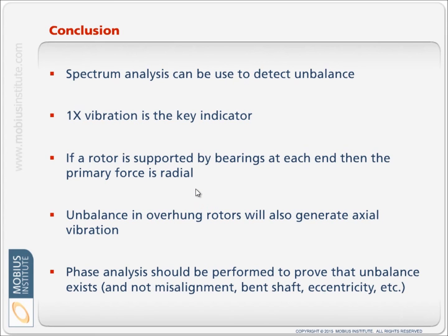If it's an overhung rotor, then we expect to see the axial vibration as well. And so between the spectrum and phase readings, we get a good diagnosis. The time waveform should just be a simple sine wave, so it's not a real good key indicator.